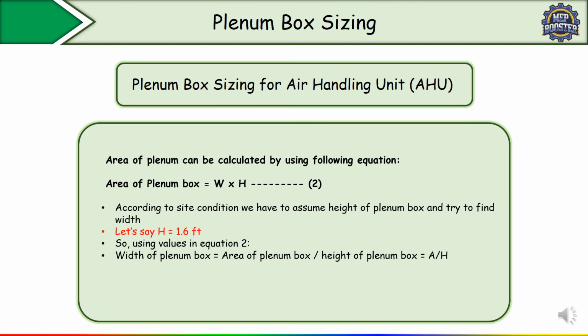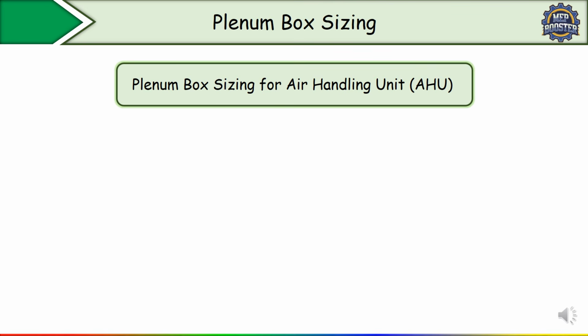Okay, to find out the width of the plenum box, we divide the area of the plenum box by the height. The area we have already calculated is 4 square feet, divided by the height of 1.6. So the width of the plenum box is 2.5 feet, and the height we have considered is 1.6 feet. In the same way, now we need to calculate the depth of the plenum box.